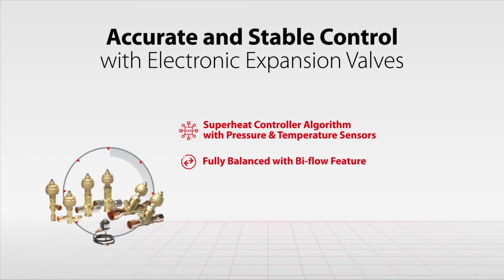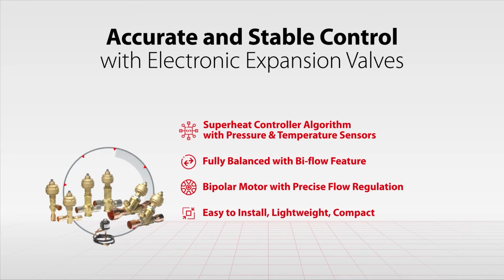With Danfoss Superheat controller algorithm and pressure and temperature sensors, the valves are designed for precise liquid injection in evaporators. The valve is fully balanced, providing a biflow feature as well as a solenoid tight shutoff function in both flow directions. The valve design uses a bipolar motor to provide precise flow regulation. They are easy to install, compact, lightweight, and work with all common refrigerants.